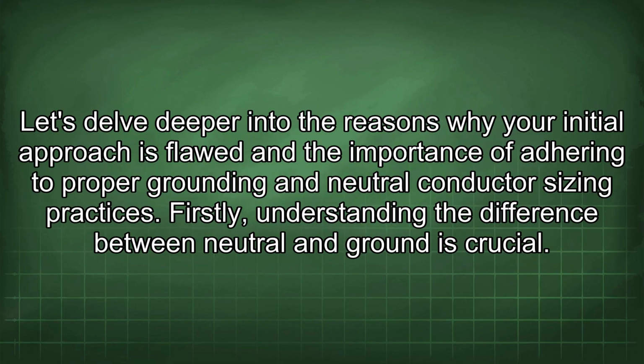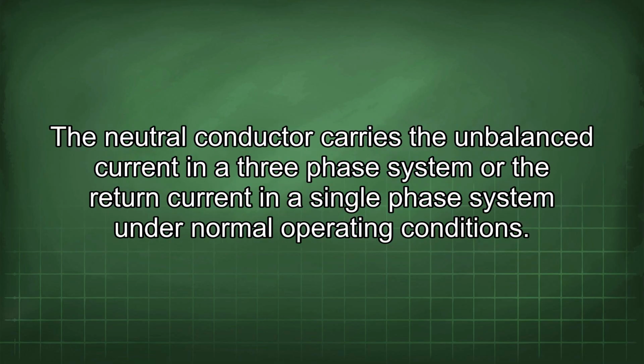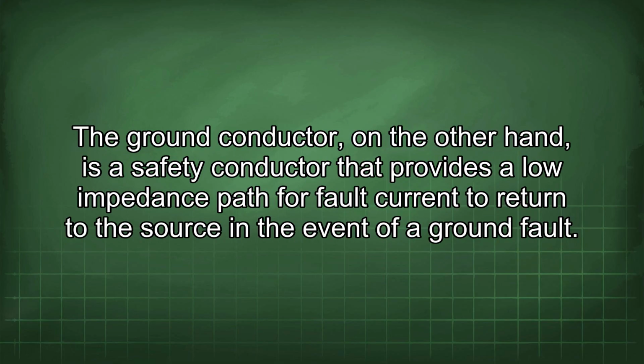Let's delve deeper into the reasons why your initial approach is flawed and the importance of adhering to proper grounding and neutral conductor sizing practices. Firstly, understanding the difference between neutral and ground is crucial. The neutral conductor carries the unbalanced current in a 3-phase system or the return current in a single-phase system under normal operating conditions. The ground conductor, on the other hand, is a safety conductor that provides a low impedance path for fault current to return to the source in the event of a ground fault.